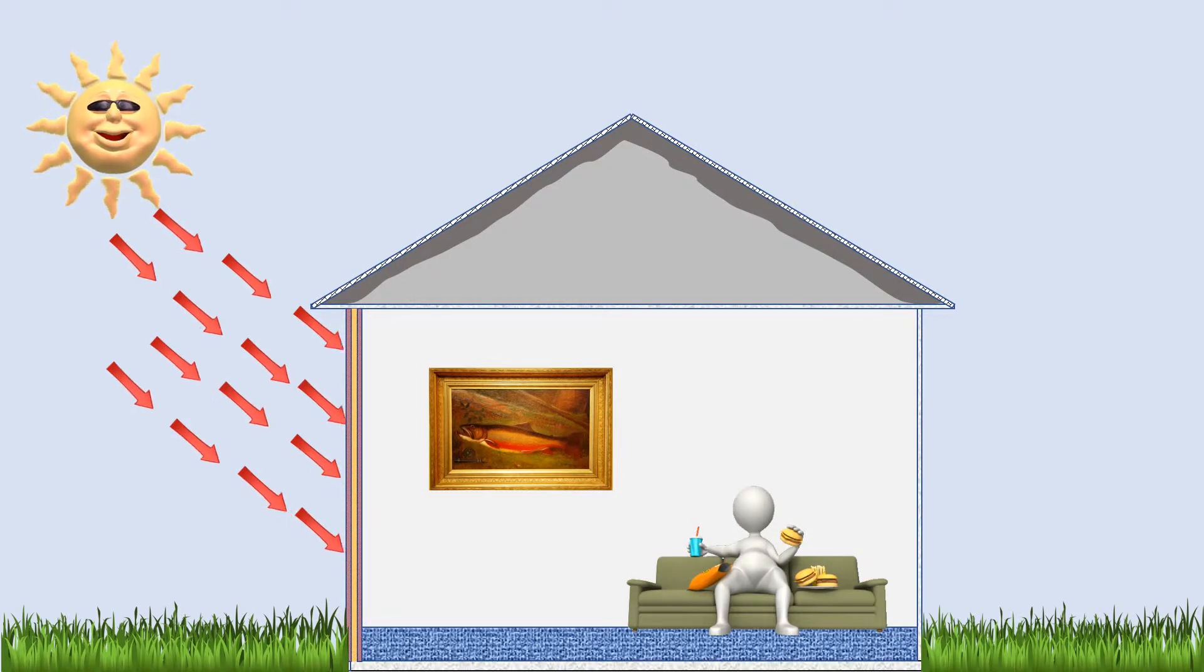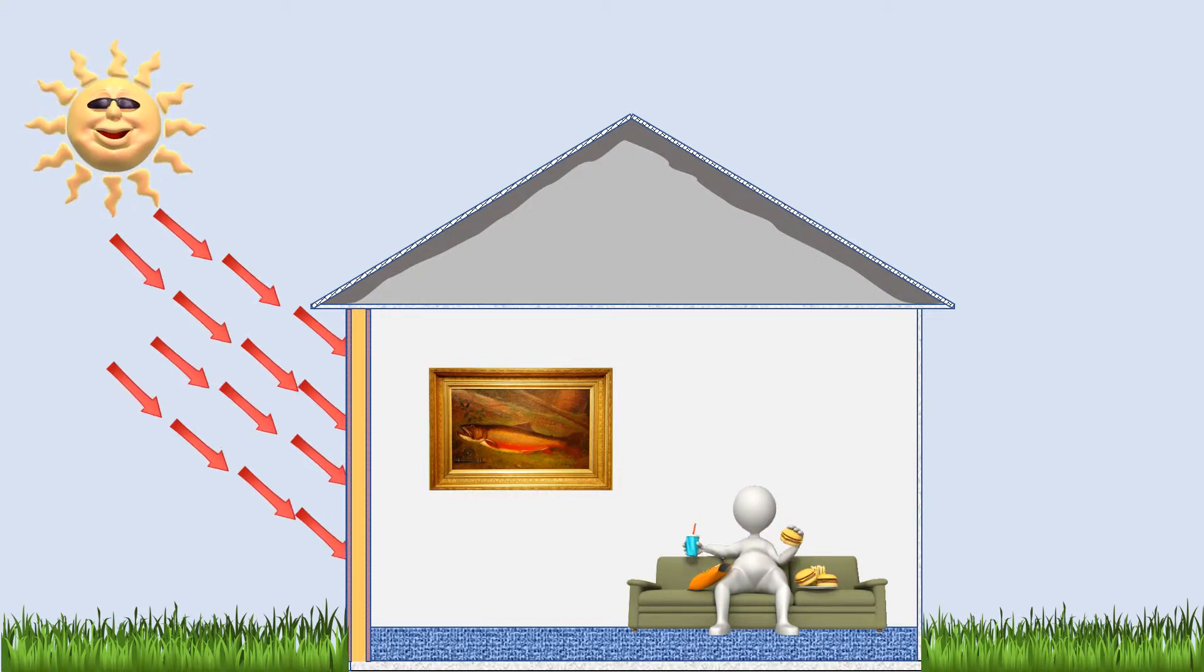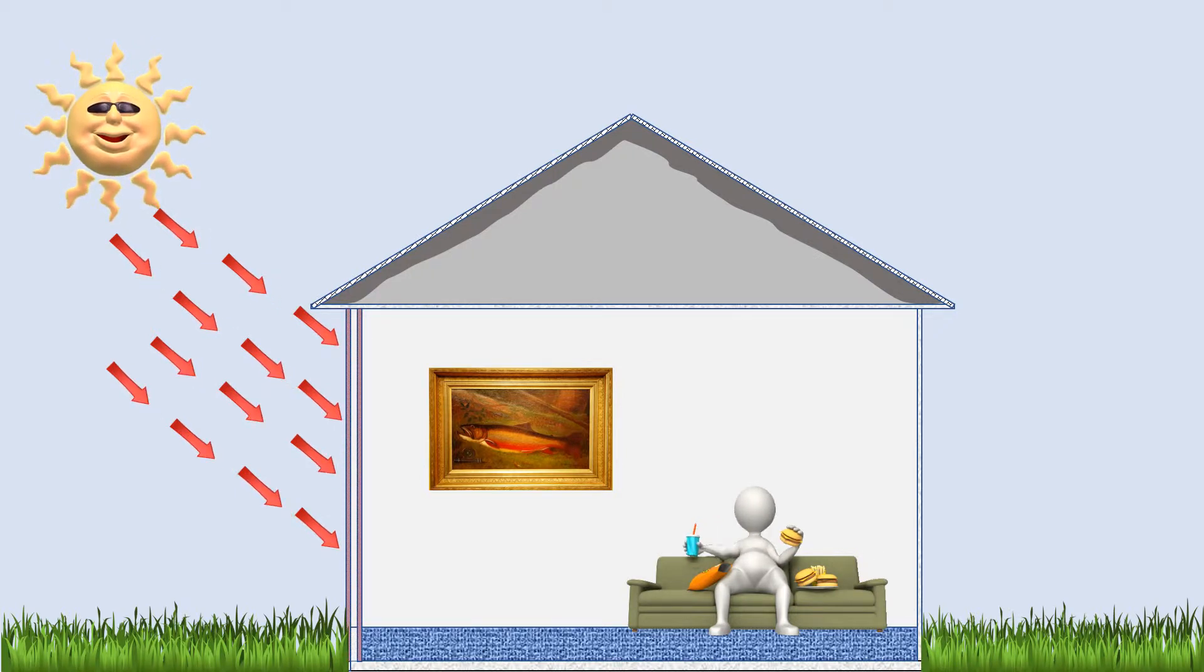So a 2x4 wall with R13 insulation will allow more heat into the building than a 2x6 wall with R20. And just like the roof, the color of the walls makes a huge difference also. Again, years ago we didn't insulate walls as much, if at all, so four or five hundred square feet per ton worked.